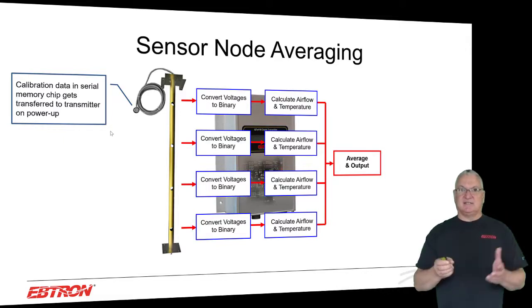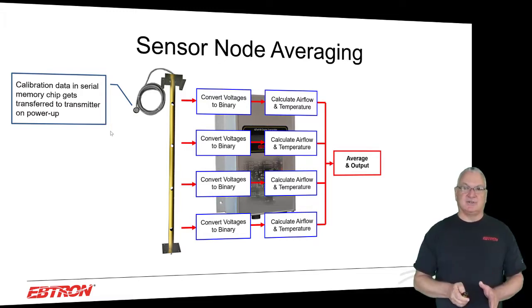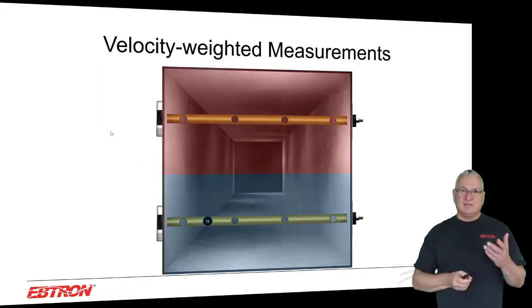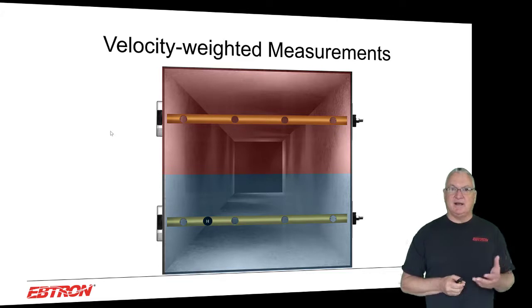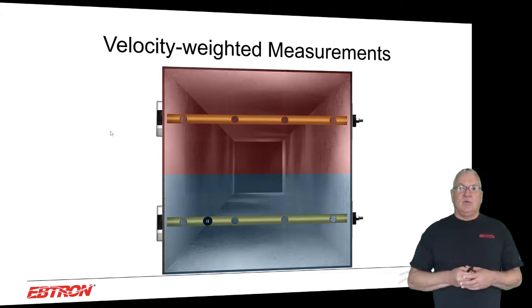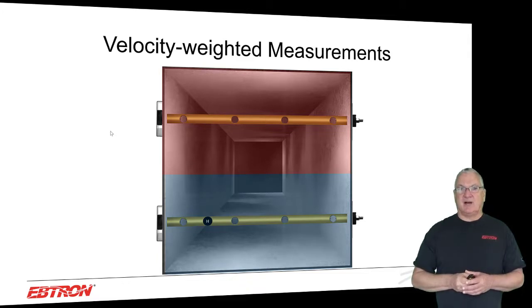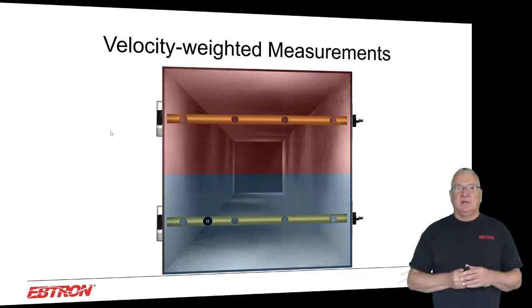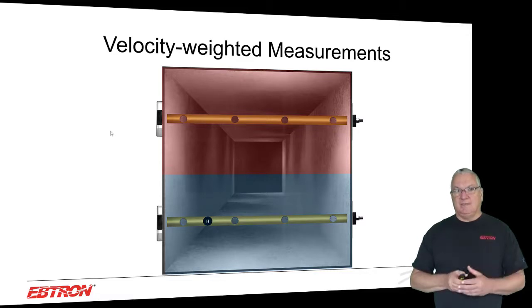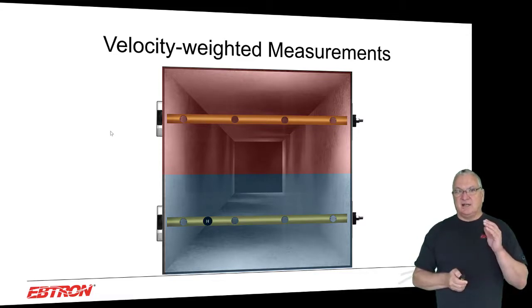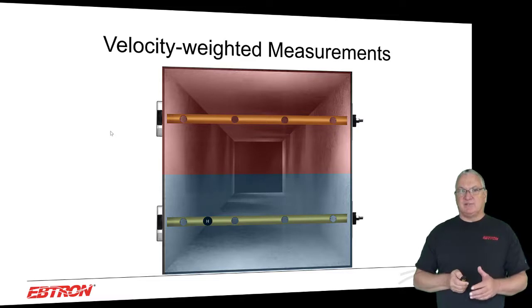If you have a 16 sensor node EBTRON, you effectively have 16 airflow sensors and 16 temperature sensors. All right, so it's true sensor averaging. This is something I want you to understand that you may not recognize the importance of. We're not just an airflow meter. We also provide psychrometric measurements, so we do velocity weighted measurements. And this is going to go quick, so you may not grab this first pass, okay?